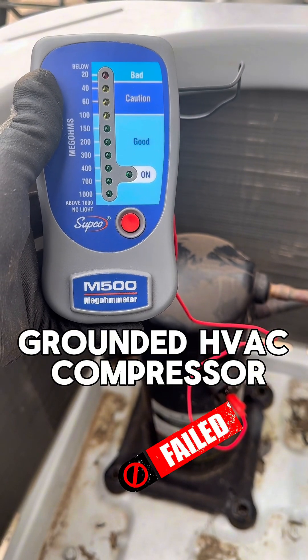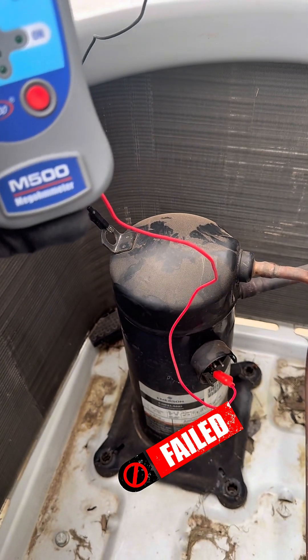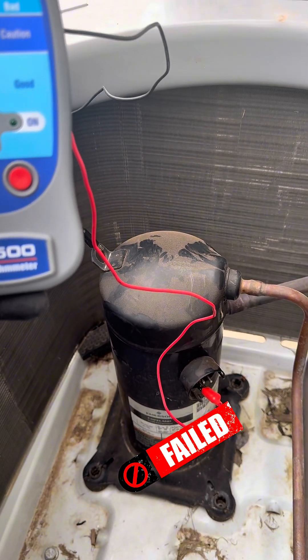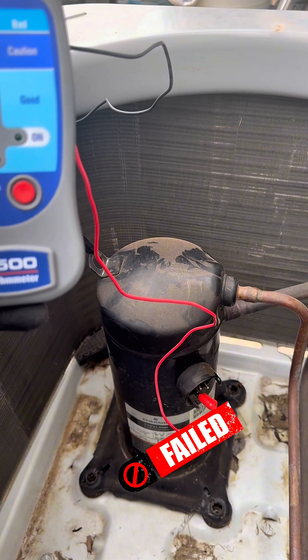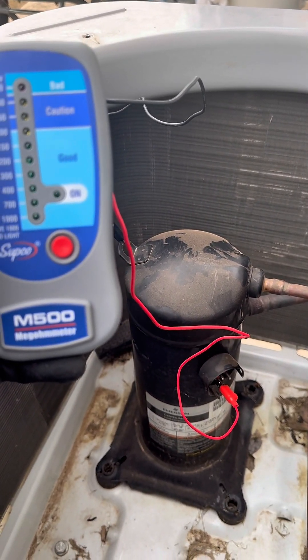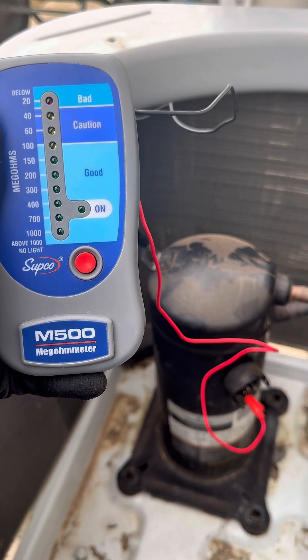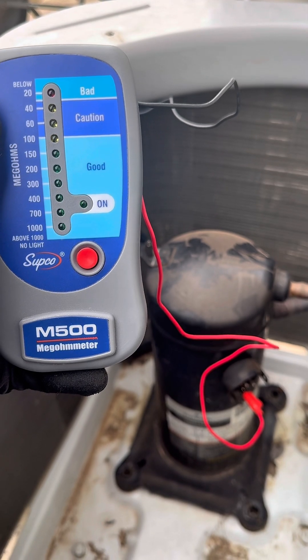Hello HVAC fans, just a quick video on the Supco M500 Megohmmeter. So we have here a shorted compressor. The windings are shorted to ground. I actually confirmed it the other day with my multimeter and am coming back today to swap it out.